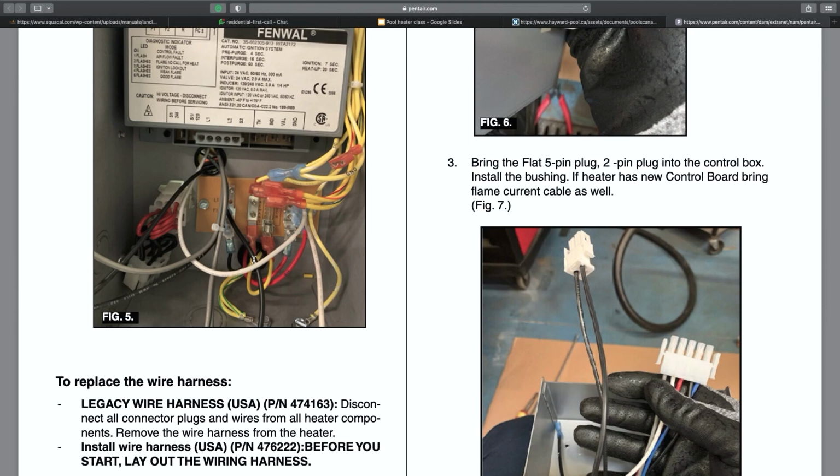And so you could be chasing a no display, chasing power problems way too long, and then at some point you realize, oh, right here next to the fuse, my control wires are hooked up. This has an external controller that needs to be turned on for me to see any display. As soon as it turns on, the heater doesn't have a remote or regular mode, it's just on off for this heater. So as soon as it turns on, you need to also check, what's my temperature set at?